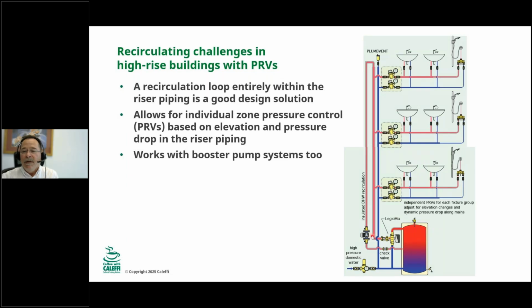The cold water goes through a set of PRVs to serve a particular zone. This could be a group, maybe 1 or 2 or 3 or 4 levels, or it could be 4 or 5 apartments, whatever. But we have PRVs here, and we're running a high pressure riser with PRVs to serve the zones. So this is one way to do it, right? Recirculate here. All the recirc is located on this side of the PRVs. You could have a high pressure system. You could have booster pumps here too, and your recirc system is going to be piped the same way. There might be some questions on this one, and we'll get to them as they come in.